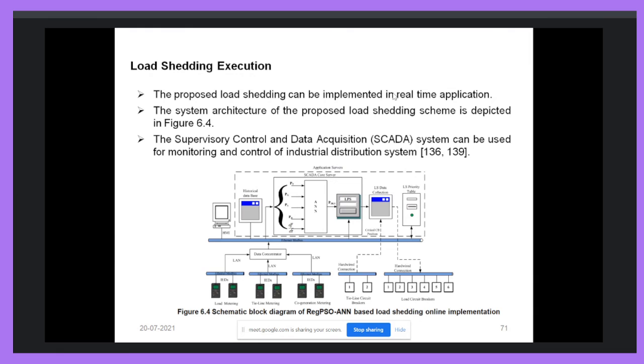Now this is how we can implement this artificial neural network in real time for load shedding purposes. Here you can see this will all be done with the help of SCADA and a server. In the SCADA server, we install the artificial neural network software and give the inputs in real time. Whatever output we get from the artificial neural network is processed, and on the basis of the priority of the loads we have decided to disconnect, the loads are disconnected with a tripping signal provided to the circuit breaker. Here you can see the schematic. This is how we can implement the artificial neural network in a real system.